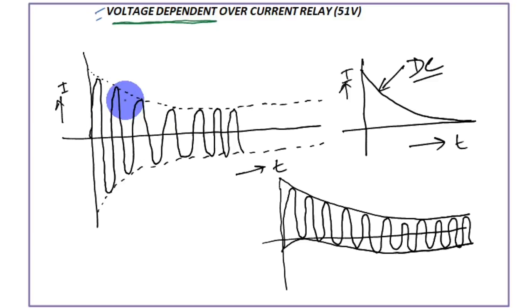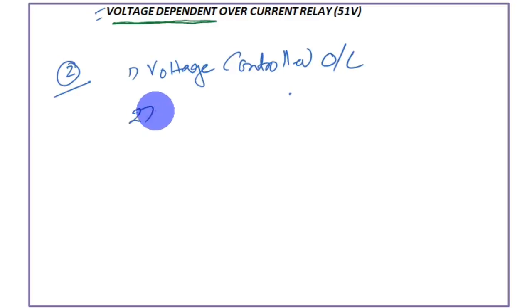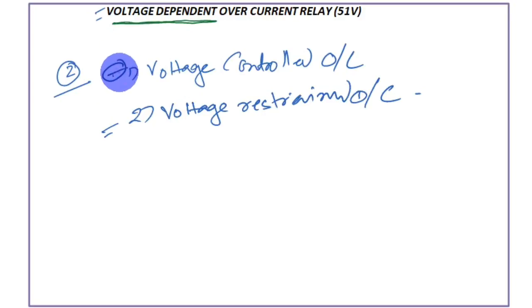You can see there is a huge variation of fault current — even without the DC component, the generator itself has a variation of fault current. That is why conventional overcurrent protection is not adequate for successful generator protection. This is why voltage dependent overcurrent protections are introduced. There are two types: number one is the voltage controlled overcurrent relay, and number two is the voltage restrained overcurrent relay.